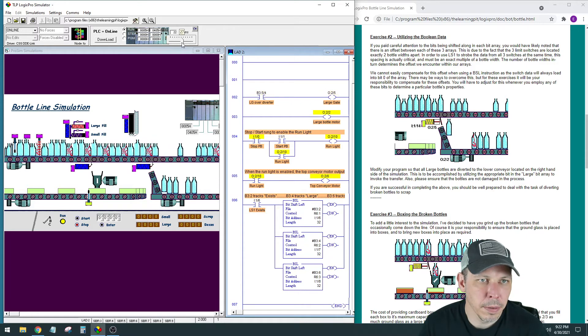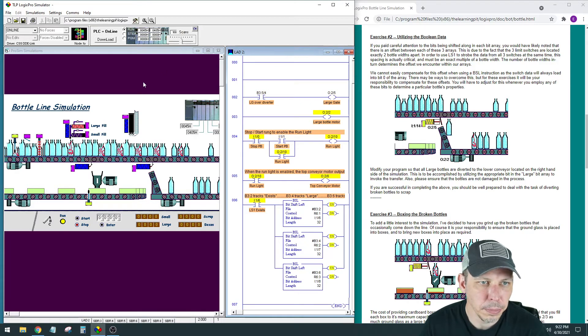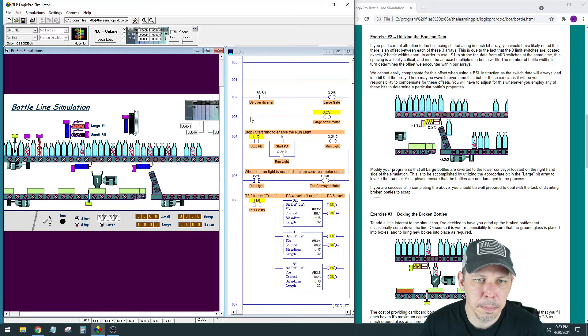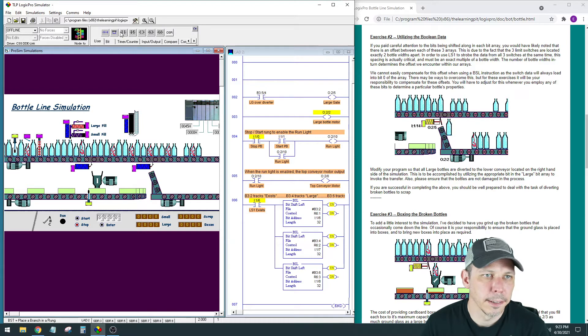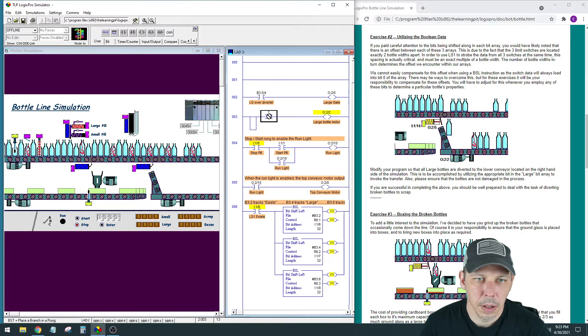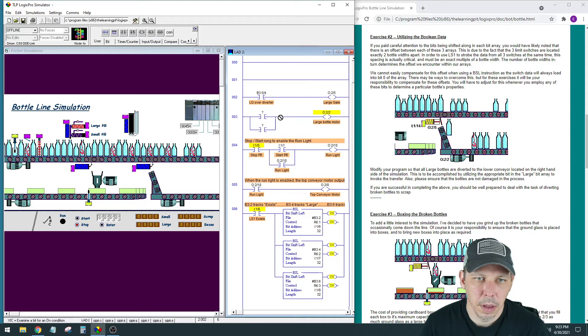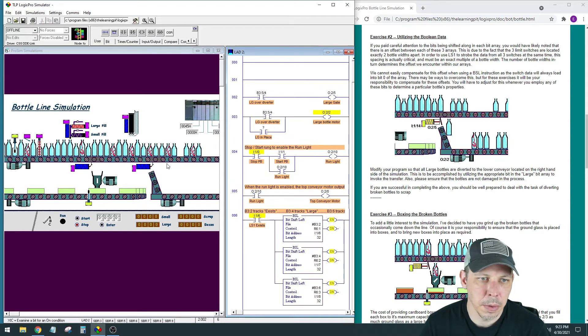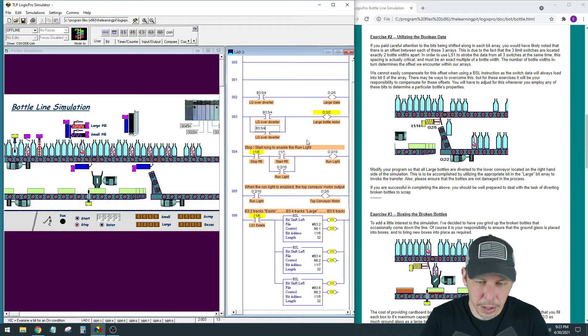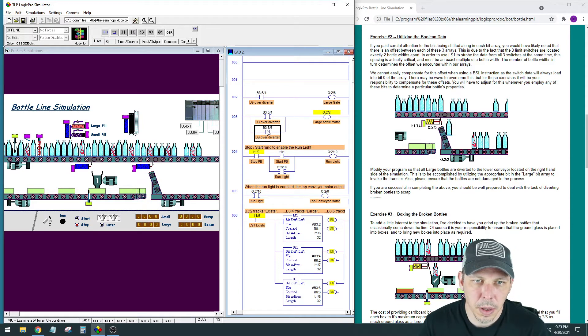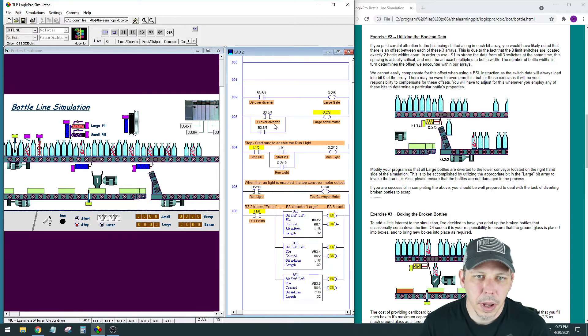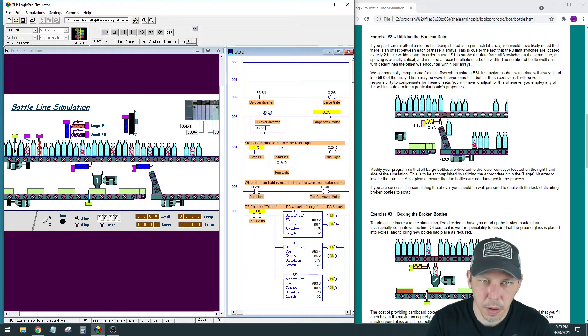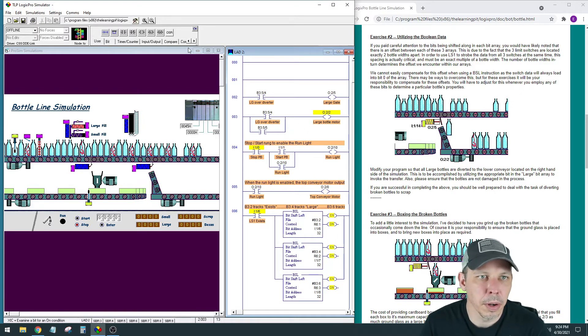And then if you want to get fancy, you can make this conveyor only run at certain times instead of all the time. That's not required, but that's our large bottle motor. And we could put that guy, and we'll put that in there. And we're going to run it anytime there's something right above it, and we're also going to run it a little bit before or after. And then I had that old name in there, so I'm going to edit that. So now anytime there's a large bottle at four or five, it'll increment this by one bottle. So let's see if that'll work right.